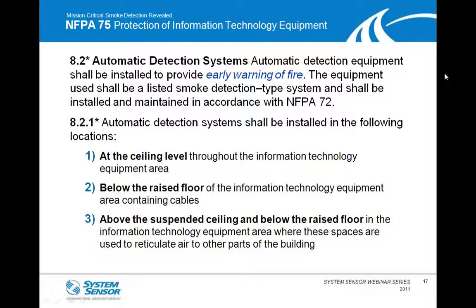A, at the ceiling, throughout that information technology equipment area. B, below a raised floor, in any area that would be containing cables or transmission cables. And 3, above the ceiling and below the raised floor, where these spaces are used to recirculate air to other parts of the building.